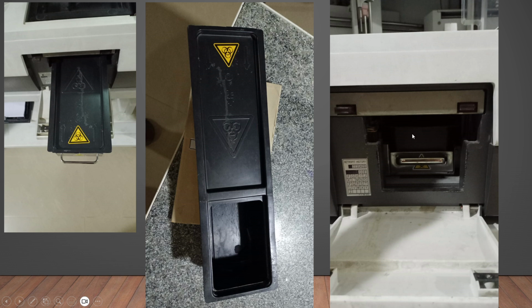And always remember that it will always shake, to make sure that the cups and tips are uniformly dumped in this instrument. If you have not kept it properly, or if you have done the opposite of this, every cup and tip will fall on this, and during shaking it will go here and there, and the instrument will get totally stuck. Totally means totally, then the whole instrument needs to be opened up to remove all the cups and tips. It will become a disaster. So you have to ensure that this open end only goes inside, and this remains outside, and it is properly put, and it will always shake to make sure the cups and tips are uniformly distributed inside.